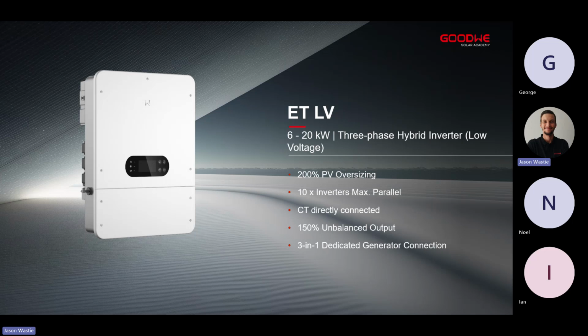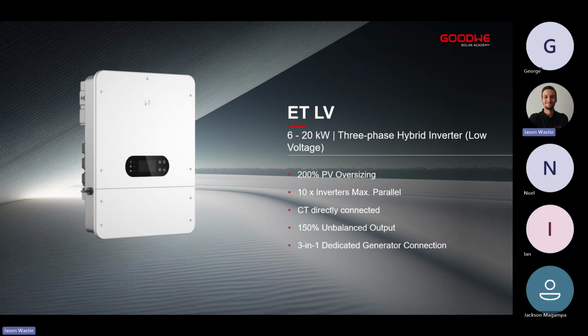So we can unbalance the outputs. It's extremely difficult at sizes, installations or sites of this size to have only three-phase loads generally. So we can balance our single-phase loads. It's very difficult, obviously, to always be completely conscious and mindful of how much load we're putting on each phase. I know if I had to live in a house with three-phase power, I wouldn't be too concerned or too worried about which phase I'm putting power on every time I turn something on in the house. So having a completely balanced system is near impossible. That's why we've got the unbalanced output.